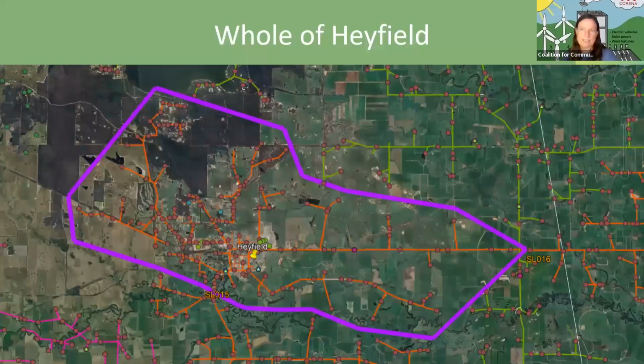Reliability was one of our concerns. So we chose two disconnection points - the one I showed you earlier, and a second one - because the more lines you have in your microgrid, the more likely it is that the fault causing the outage will occur inside your microgrid. Lines are prone to storms and weather.